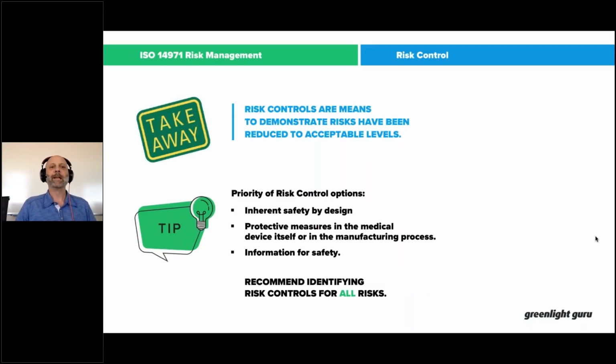It's the whole idea. And I need to make sure that I'm factoring in three levels when it comes to risk controls. I know the most common approach that most people get to, and I think usually the reason is because we start risk way too late in the process, is to slap it on the label, put it in the IFU, the instructions for use, put a warning sticker on it. Folks, labeling is a last resort when it comes to risk control. We shouldn't just be slapping a label or adding some statement in the instructions for use. If you start risk too late in your design and development process, sometimes that's what you're left with. That's the only option you have because the product has already been designed and tested.